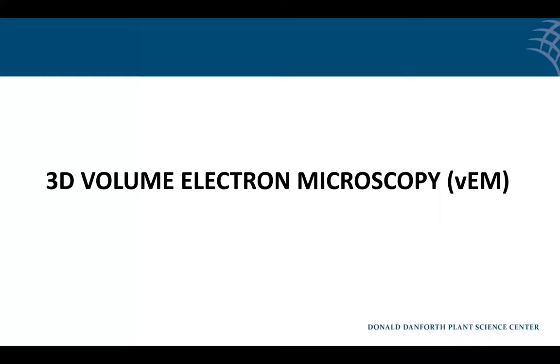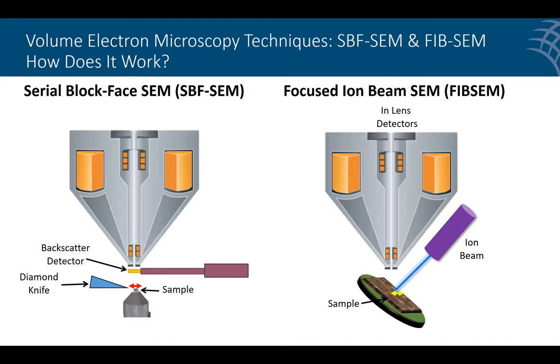My final topic is volume electron microscopy. Array tomography is considered volume EM, but here I'm talking about techniques where we keep the block intact and image the block face. One technique is called serial block face SEM — there's actually a diamond knife microtome inside the SEM chamber, and it removes very thin layers, then the electron beam scans across and creates an image from backscatter signals. With focused ion beam SEM, rather than a physical knife, a gallium ion beam repeatedly scans back and forth, removing only a few nanometers at a time, and you image the block face in backscatter mode to build up three-dimensional volumes.